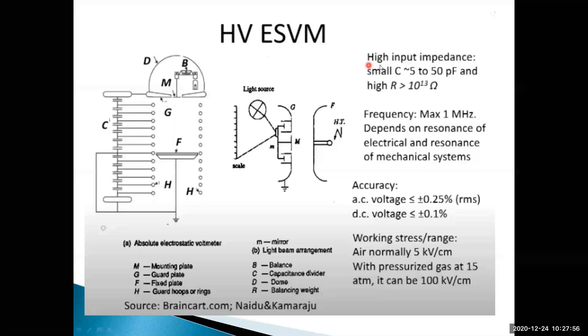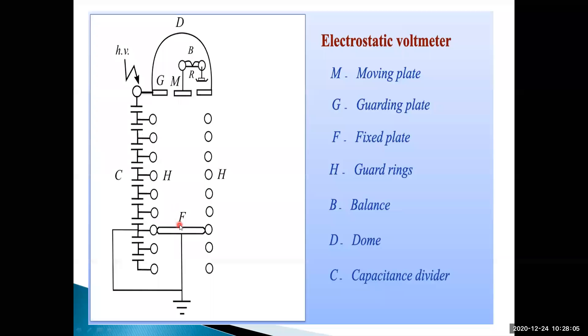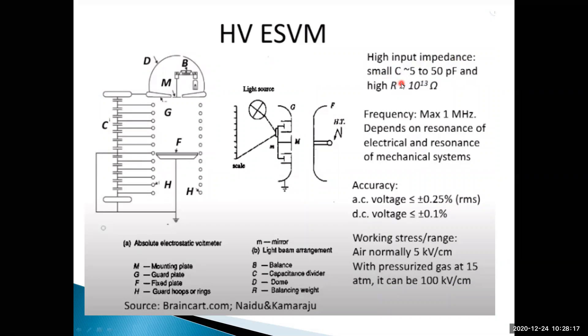This high voltage electrostatic voltmeter has high input impedance, because there is a large gap between the moving plate and fixed plate - it is essentially open circuit. High input impedance with small capacitance in the range of 5 to 50 picofarads, and high resistance greater than 10 to the power of 13 ohms. Frequency is limited to a maximum of one megahertz.